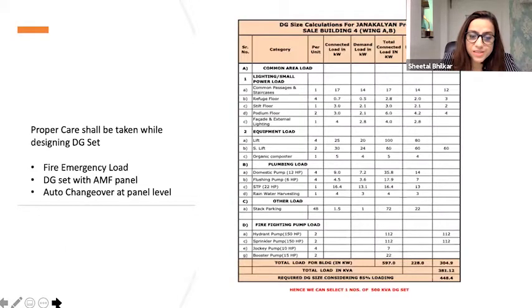Then in case of DG set also, the selection of DG set is very important for high rises, because when you do the DG set calculation, you have to consider the load in fire condition, and in that way only you have to select the DG set. You just can't select the DG set considering common area load. You have to consider firefighting load and starting current of the highest motor while designing your DG set. This is a very important factor.